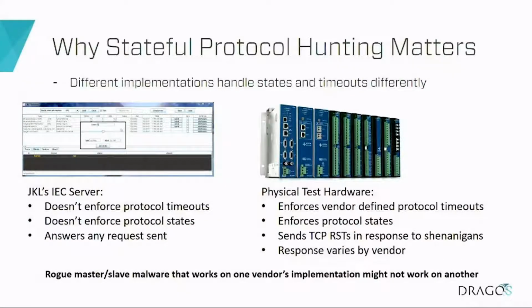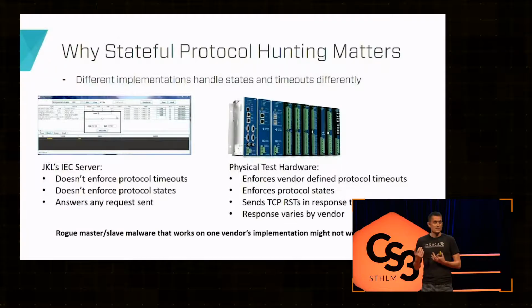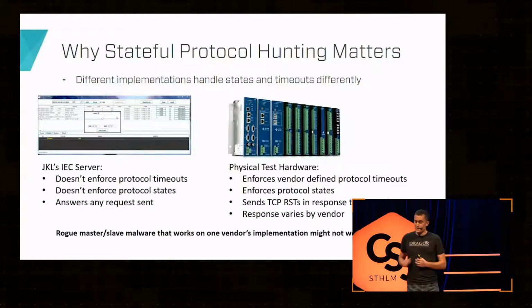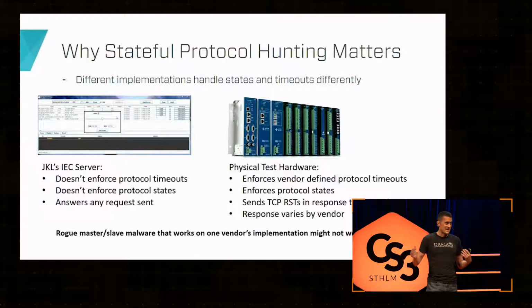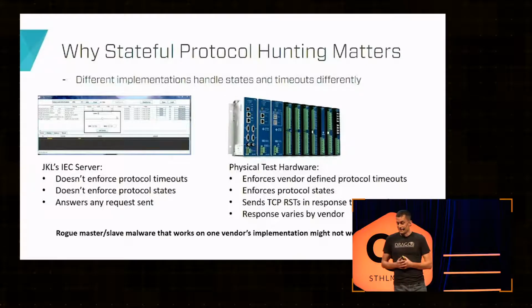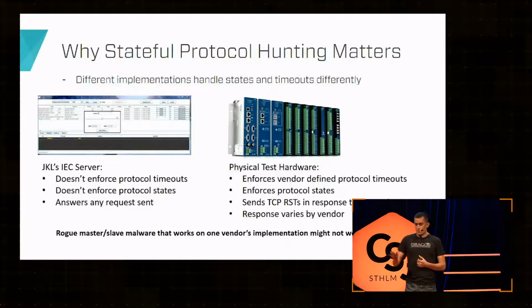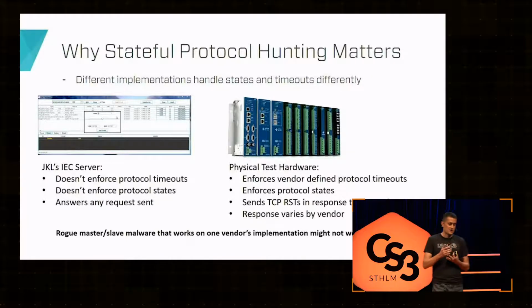This allows you to see the different states regardless of what the physical systems are doing. As I said, when we were testing, we were using the SEL gear on the right. If you use physical hardware, it's going to rely on that vendor-defined protocol timeout. An interesting thing is Crash Override's 104 module is really slow, and some of the commands that we saw were actually outside of the timeout range. Attackers either didn't know the timing or how we were running it, and just didn't get the command back in time. So when you're running on physical hardware, you're constrained by the timeouts.